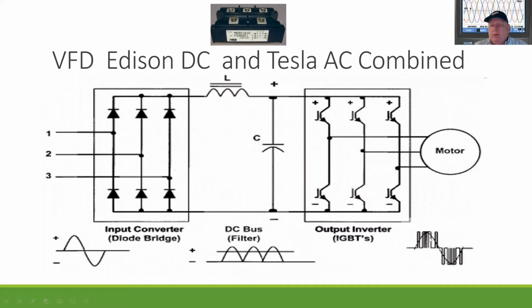And we can also control the amplitude of voltage. So what a VFD does is it converts from AC to DC, then back to AC with transistors that are fed to the motor. And that's really the main combination of a variable frequency drive. And that all came about because of this device at the top here, which is a transistor. Transistors were really developed, in large horsepower, large power, in the 70s. Both Fuji and Toshiba were very large into it.